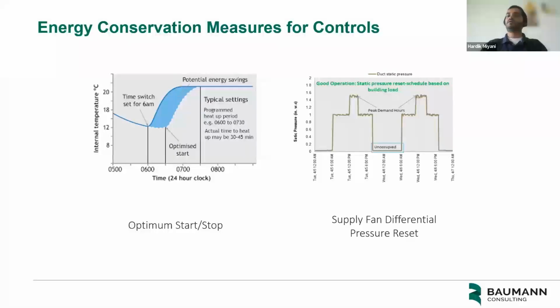And last but not the least is the supply fan differential pressure reset. What we are currently seeing in a few commercial buildings in the DC market is that they are operating these fans at a constant static pressure all the time, even when the building is less occupied. So this is a place where we can save energy by ramping the fan speed up or down. You can change the static pressure and then save energy by implementing this measure.